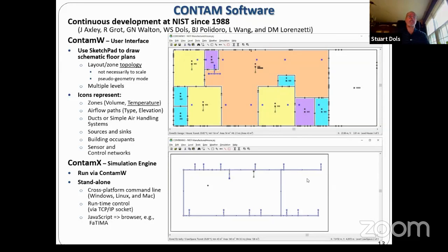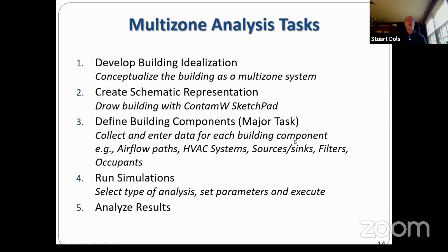The second component is the simulation engine, CONTAMX. It can be run via CONTAMW, reads in a project file, and forms a set of equations to solve. This program can operate standalone and is cross-platform — it runs on Windows, Linux, and Macintosh. It incorporates runtime control that allows execution of CONTAM and exchanging data with other programs, and it has been compiled into a JavaScript program so it can run in a browser, which is what FATIMA is actually using. Tasks for running multi-zone analysis include developing a building idealization, creating a schematic representation, and defining building components — this is probably the most significant task in any analysis.